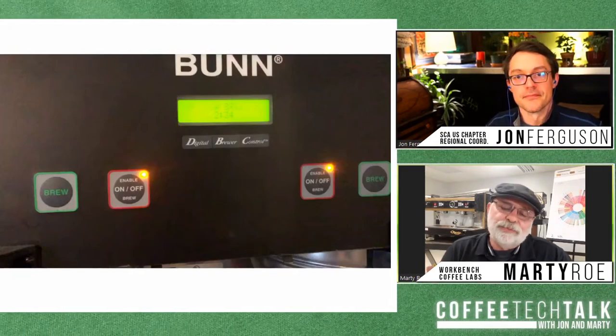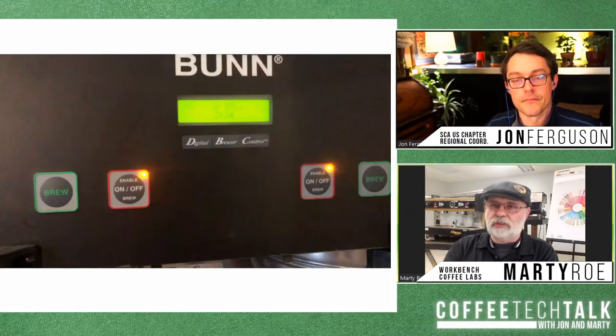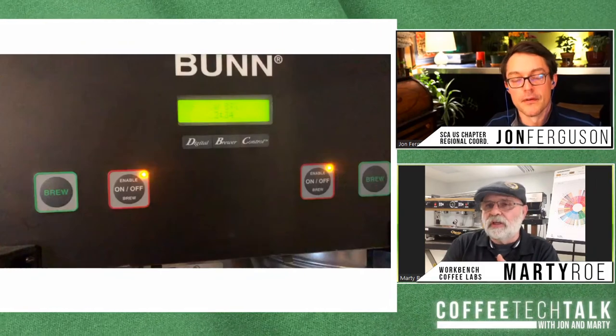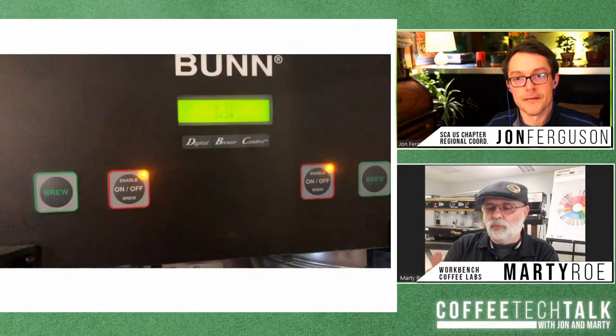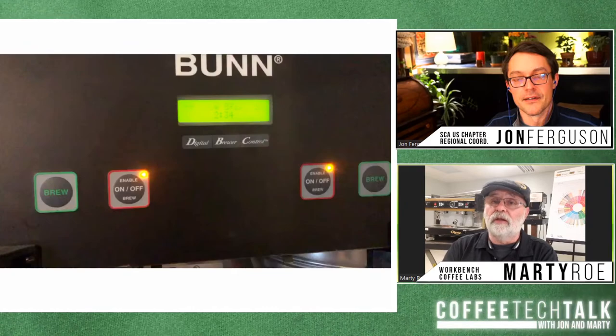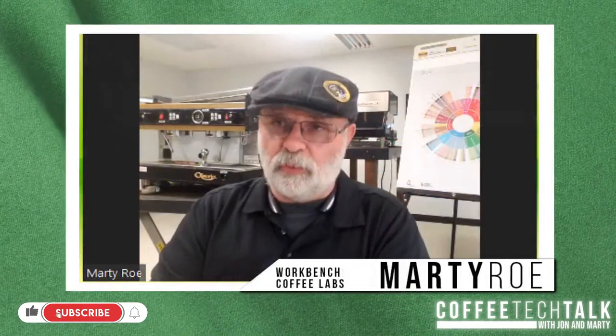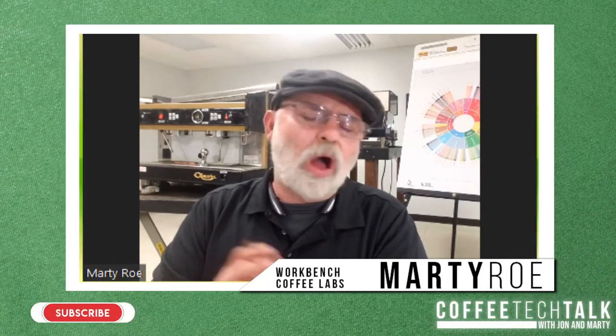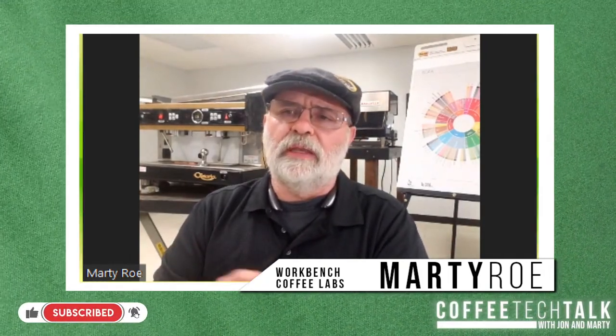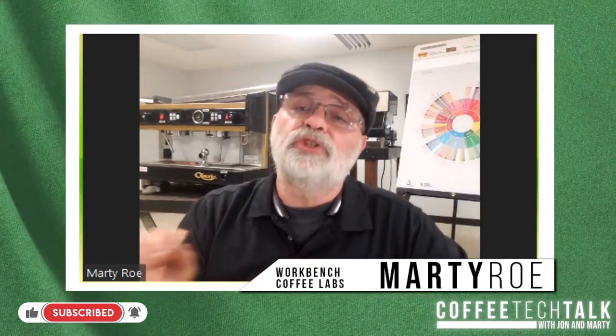Okay, the bottom line is, those coils can get loose internally. And you're sending it AC voltage, so it's going to be vibrating regardless. Most of the time you can't hear it. So is it on its way to failing? It's on its way to being annoying. Ultimately it can fail, I guess, if you go long enough, but it's going to be much more annoying than anything. What's happening is it's generated enough space in there between the coil and the metal structure that's holding it in. But what you have to do is listen to it.